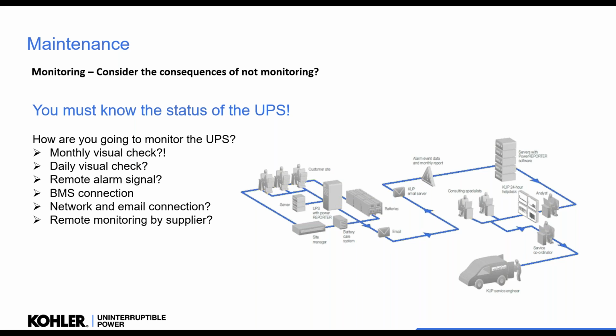We're going to put a UPS in there, but it must be monitored. There's no point sticking it in a dirty, horrible plant room and expecting it to be working the next time we use it, unless we do some checks on it, maintain it, and know what status it is in. Very easy nowadays to connect a UPS to BMS, actually to the network, and it will alarm out by email and can even be remotely monitored by the supplier as well. So we know exactly if it's going to work when you need it.